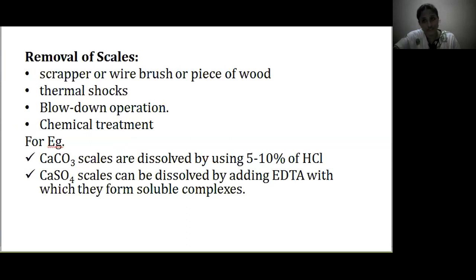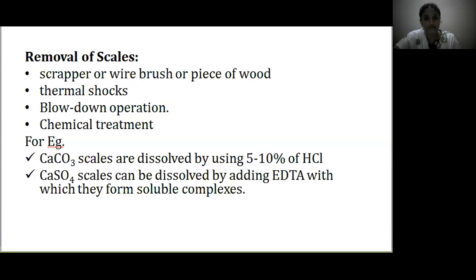How can we remove scales? At an early stage, scrapers, wire brushes, or pieces of wood can be used. Thermal shocks — increasing or decreasing the temperature — can also help. If the scales are loosely adhering, a blow-down operation can be used. If hard and firmly adhered, chemical treatment is applied. For example, calcium carbonate scales are dissolved using 5–10% HCl, whereas calcium sulphate scales can be dissolved by adding EDTA, which forms soluble complexes.